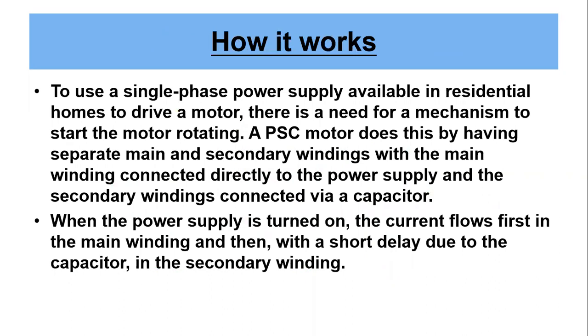To use a single phase power supply available in residential homes to drive a motor, there is a need for a mechanism to start a motor rotating. A PSC motor does this by having separate main and secondary windings, with the main winding connected directly to the power supply and the secondary winding connected via a capacitor.